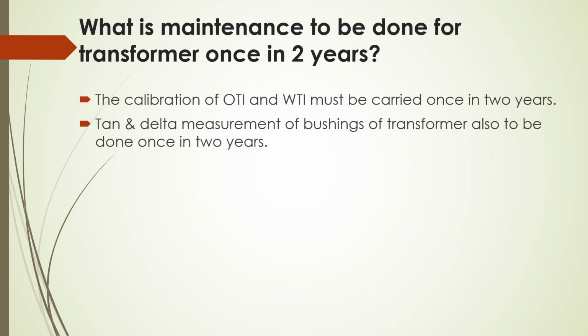What kind of maintenance is to be done for transformer once in 2 years? The calibration of OTI, that means oil temperature indicator, and WTI, that is winding temperature indicator, must be carried out once in 2 years. Tan delta measurement of bushing of transformer should also be done once in 2 years.